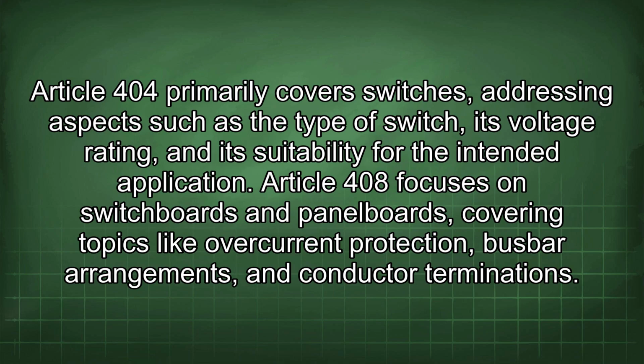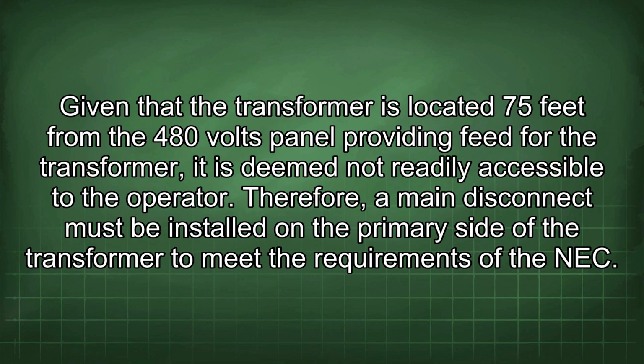Article 404 primarily covers switches, addressing aspects such as the type of switch, its voltage rating, and its suitability for the intended application. Article 408 focuses on switchboards and panelboards, covering topics like overcurrent protection, busbar arrangements, and conductor terminations. Given that the transformer is located 75 feet from the 480 volt panel providing feed for the transformer, it is deemed not readily accessible to the operator. Therefore, a main disconnect must be installed on the primary side of the transformer to meet the requirements of the NEC.